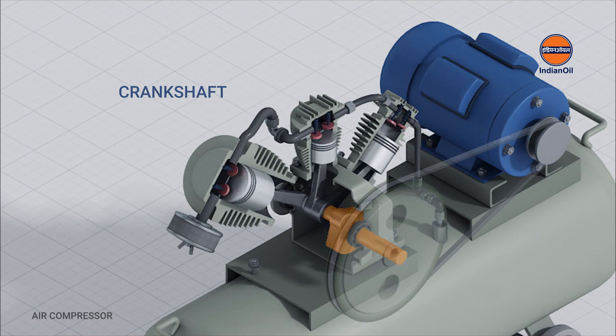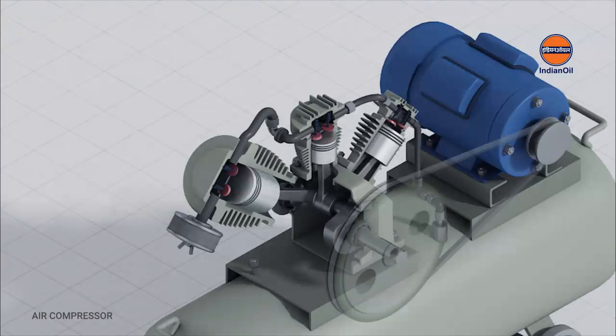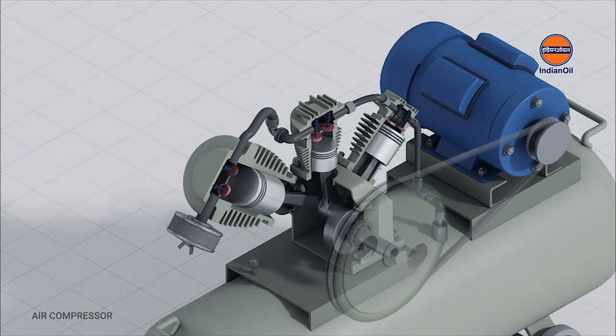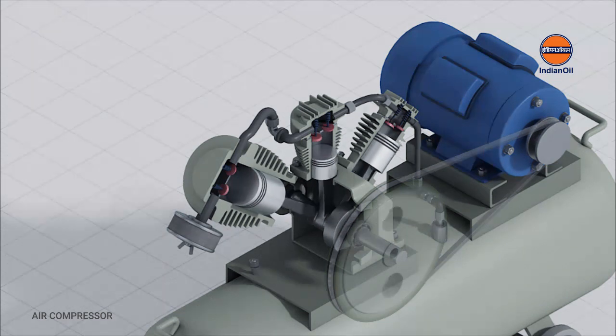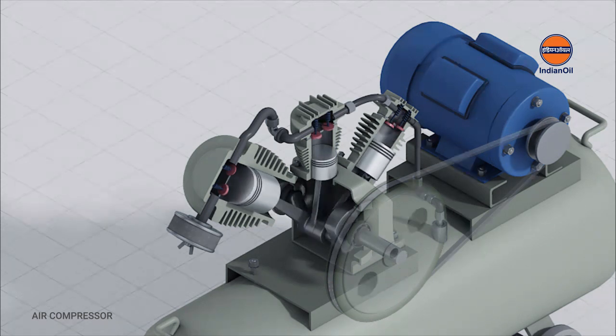Crank shaft — the crank shaft is the major shaft in a compressor, the other being a motor shaft. The shaft revolves around the frame axis and it drives the piston, piston rod, and connecting rod. Connecting rod — a connecting rod is linked between the crank shaft and piston. Valves — a compressor valve's function is to allow gas to flow in the right direction while blocking flow in an undesired direction. These valves are placed in each operating end of a cylinder — one end has inlet valves to allow gas in, while the other end features discharge valves.